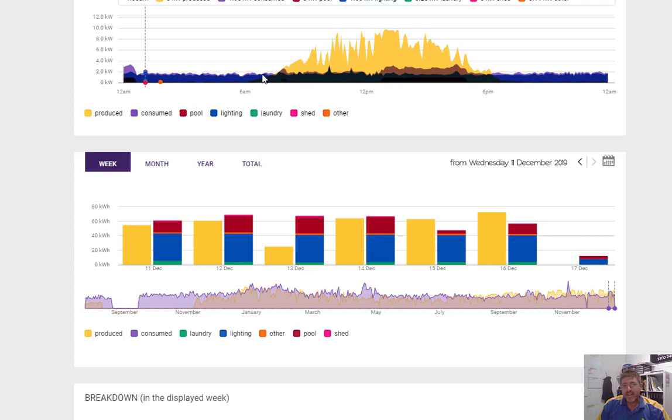So these guys have a very consistent energy load. That blue line there is the air conditioner being run, and there's just lighting as well. So that's the air conditioner being run all night long. Sometimes the best investment actually is in energy efficient appliances. This aircon is pulling 1.4 kilowatts all night long. It looks like it's not cycling. So by upgrading and putting a new air conditioner on with inverter type technology that turns on and off would save these guys some energy.